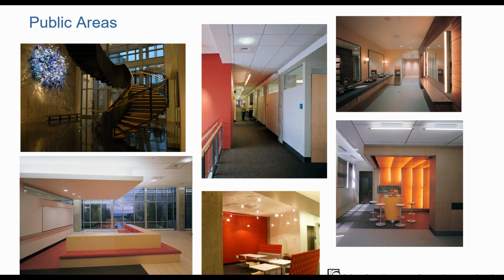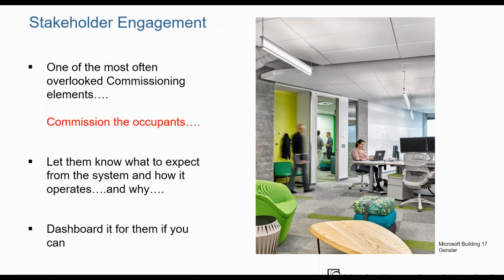We also, on this particular project, had a very early demand response system. I don't know that it ever got used, but they had the ability to diminish the lighting load by 25%. So another part of this stakeholder engagement is the idea that you really need to address the occupants post-construction. One of the most important things I think of is commissioning occupants, right?